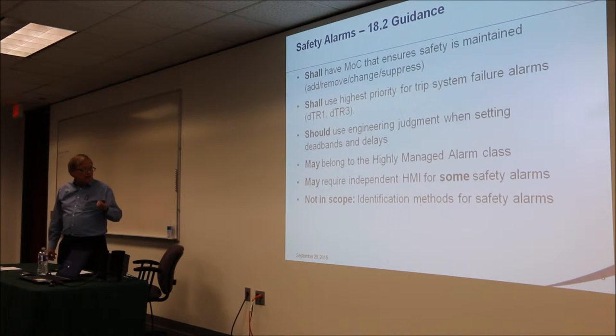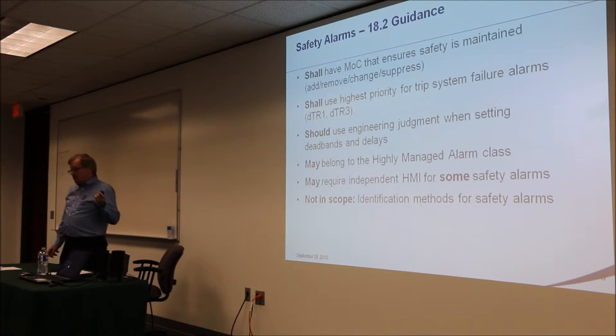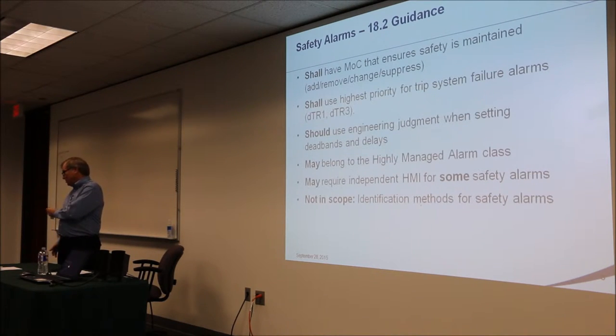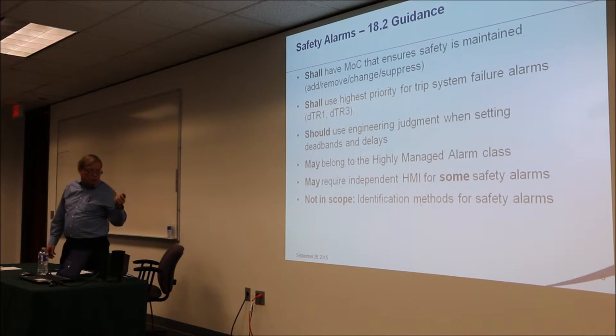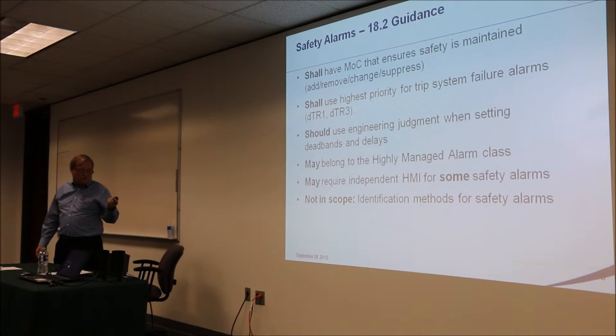Some of the shall statements: you shall have MOC, use highest priority for trip system failures, should use good engineering judgment when doing alarm design, and may belong to the highly managed alarm class. Alarm class is an attribute of an alarm different from priority — a class specifies how an alarm is managed, such as whether you're allowed to bypass or suppress it, what the MOC process is, and who has to sign off. The only class defined in detail rather than being user-defined is 'highly managed,' which was originally intended to fulfill PSM requirements. Adopting it triggers around 17 extensive requirements, and it matches up very well with what's needed for safety alarms.